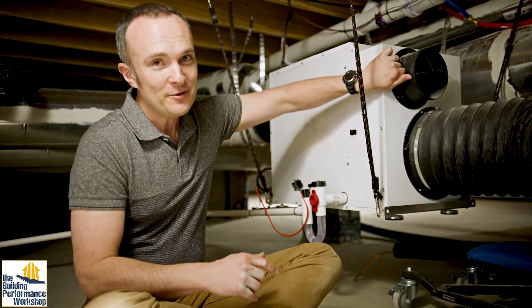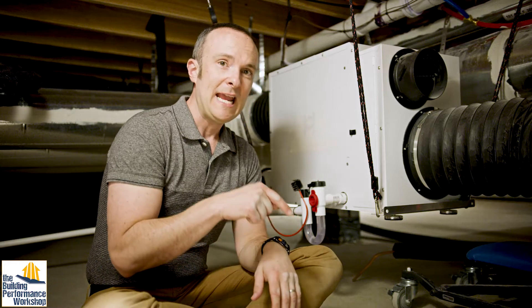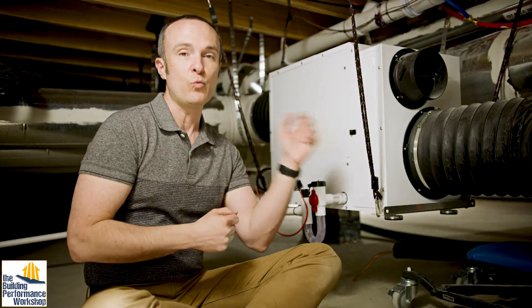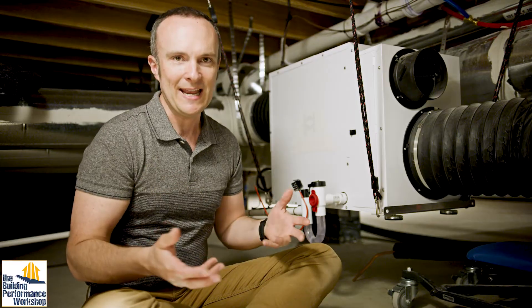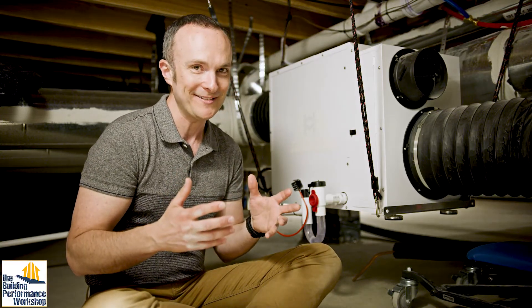In this case I don't close that damper all the way — I have it slightly open so I can depressurize the crawl space and keep air moving from the living space above down into the crawl space, which helps with circulation. Since I can't have a ceiling fan down here, you want air movement, so I've got one supply and this little bit of suction to induce pressure imbalances — tuning the home performance and making the science of this home extra sophisticated, which is both fun and interesting. Thanks for coming to my crawl space. I hope this has helped make dehumidification more interesting and maybe less complicated than it was before. Please comment if you have anything to add about the products seen here, other dehumidifiers, dehumidification techniques, or questions. Please like and subscribe — tune in next time.